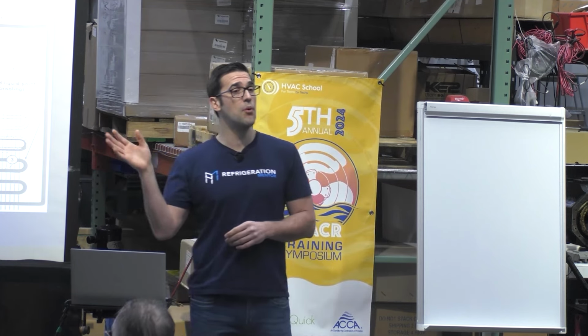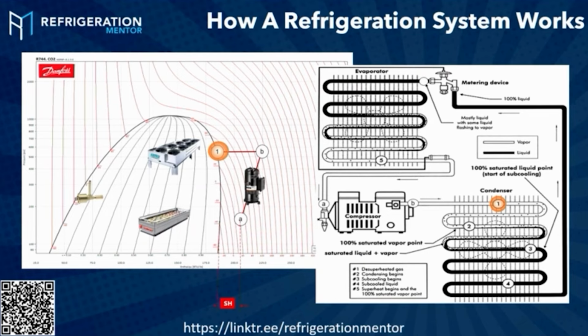This is a very important term in refrigeration. Okay? Your dew point is what you use to check what? And it's really on the bottom side of the system, but this is very important. You always use the dew point to check what in a refrigeration system coming out of the evaporator.